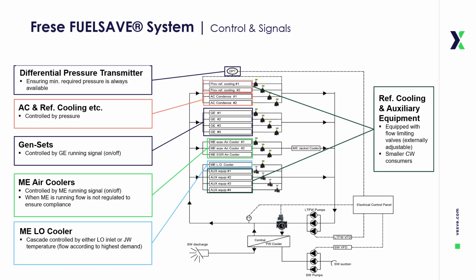Based on this data, the system adjusts pump speed through variable frequency drives and regulates dynamic control valves to match actual demand. This prevents overpumping and ensures that each consumer, whether the main engine, auxiliary engines, or secondary loads, receives the correct amount of cooling water.